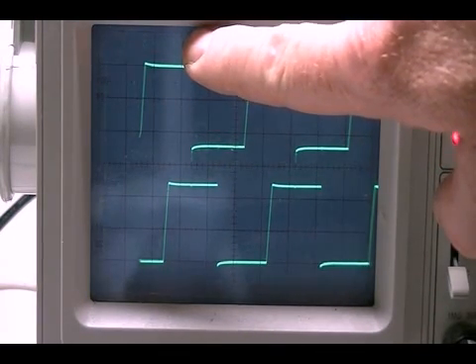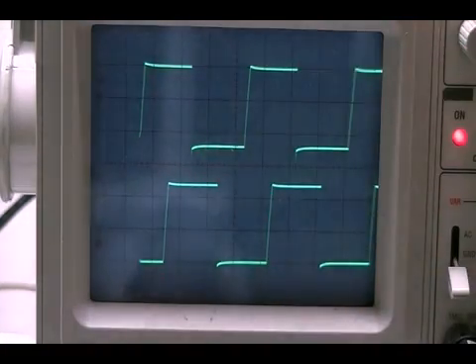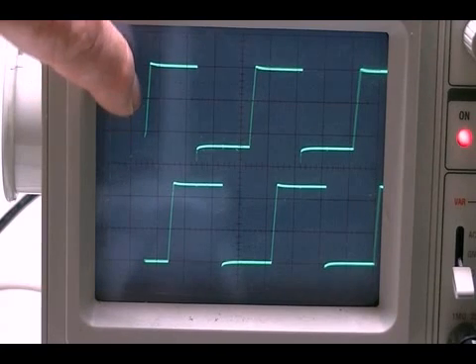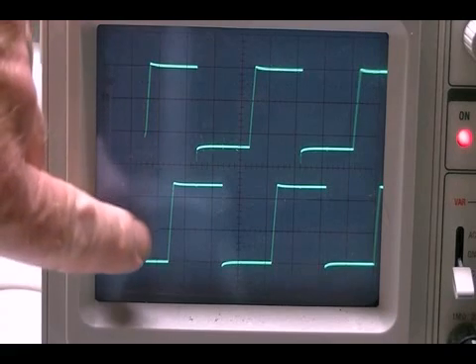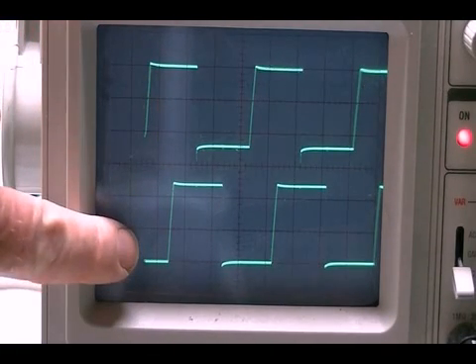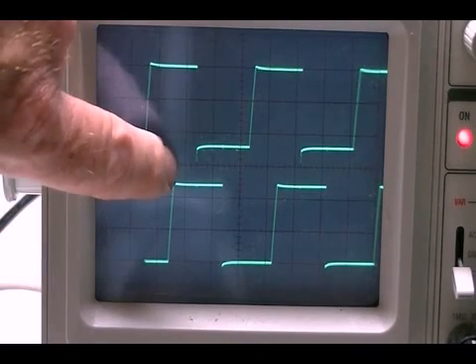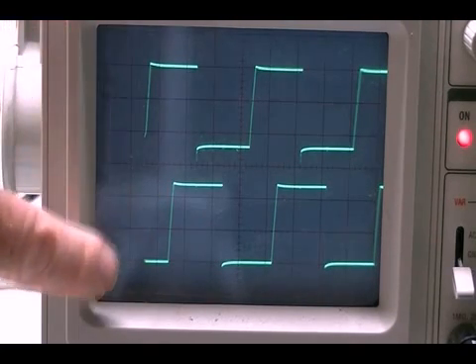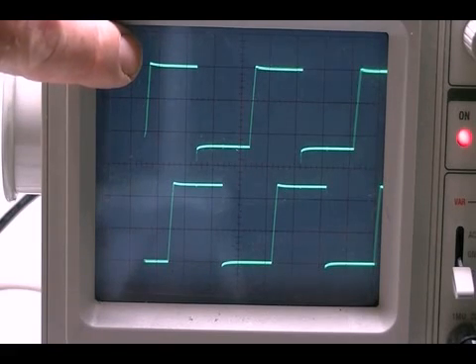It's set for two volts per division. That's not too important. What we need to do is look at the relationship between channel B and channel A. If you look at channel A, here is your rising edge. It goes from zero to five volts. But at the same point down here at B, we are still at zero volts until it's about halfway through the half cycle of channel A. This is how we know that I'm going clockwise in that particular motor setup.